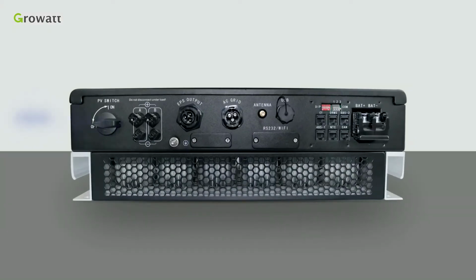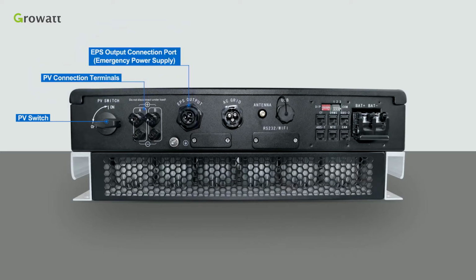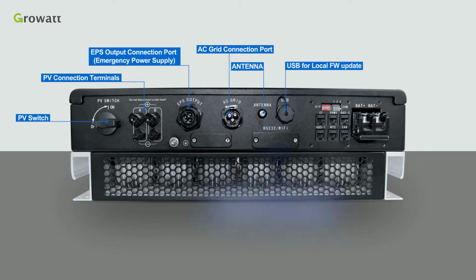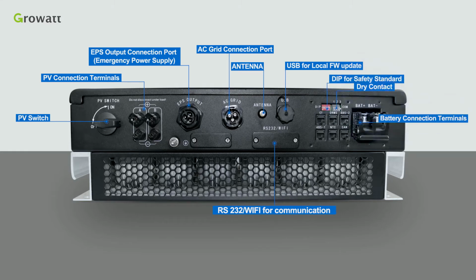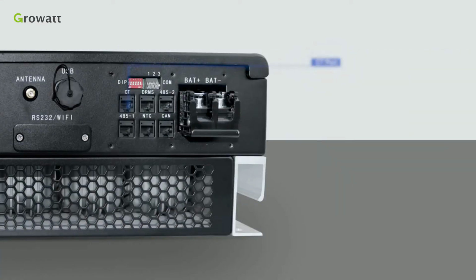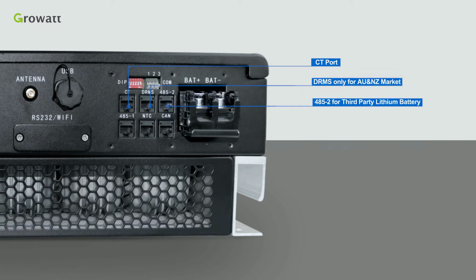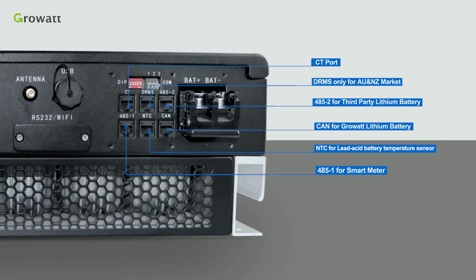There are some connection terminals including PV switch, PV connection terminals, EPS output connection port, emergency power supply, AC grid connection port, antenna, USB for local firmware update, RS-232 Wi-Fi for communication accessories, DIP for safety standard of different countries, dry contact, battery connection terminals, and communication terminals including CT port, DRMS communication port only for Australia and New Zealand market, 485-2 port to connect the third-party lithium battery, 485-1 port to communicate with a smart meter, NTC port for lead-acid battery temperature sensor, CAN port to communicate with Growatt lithium battery.